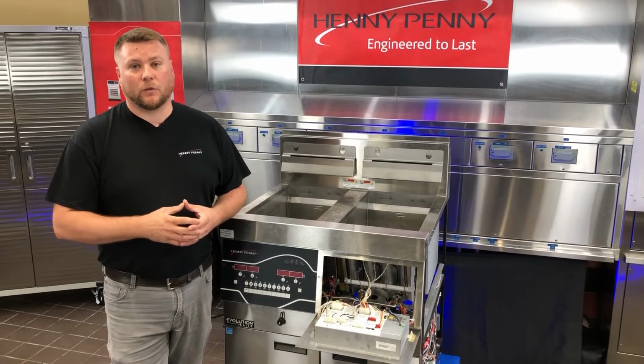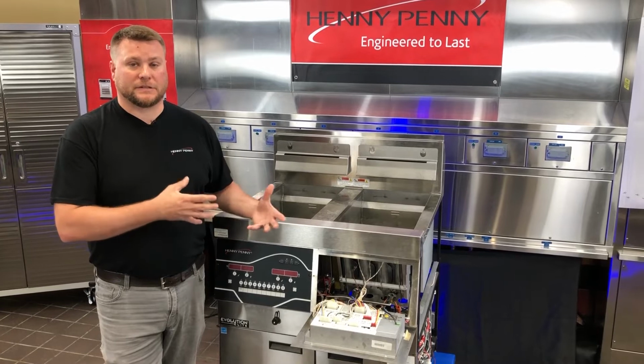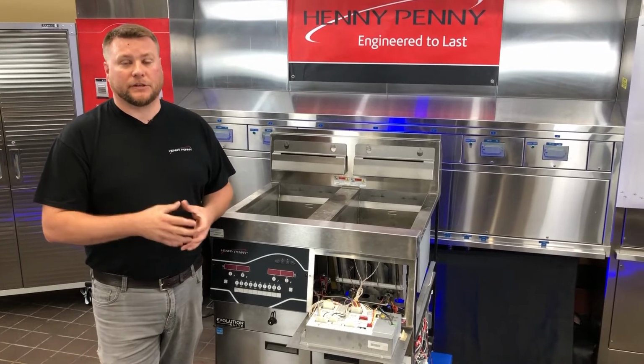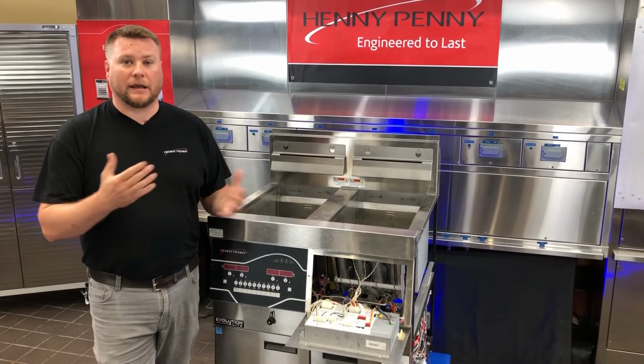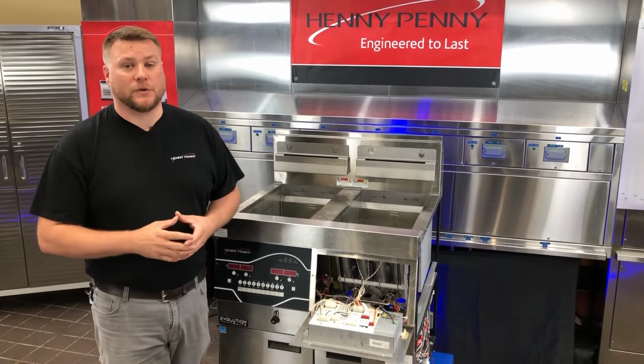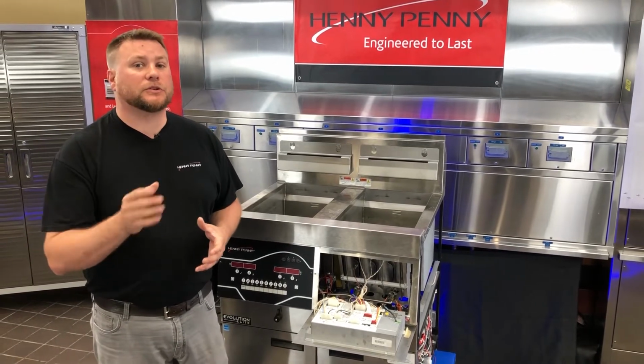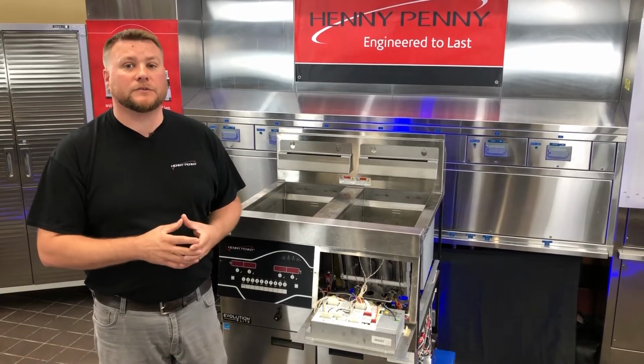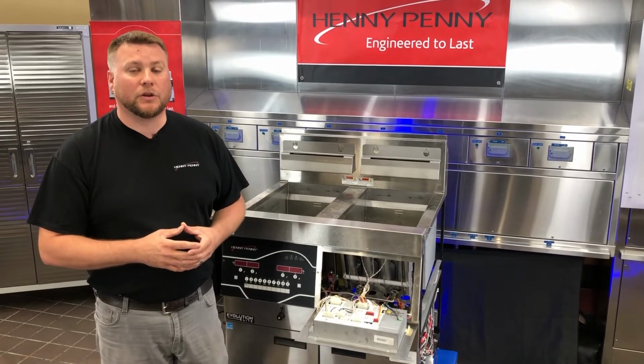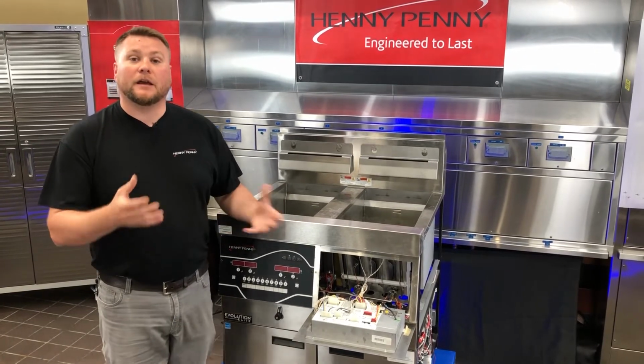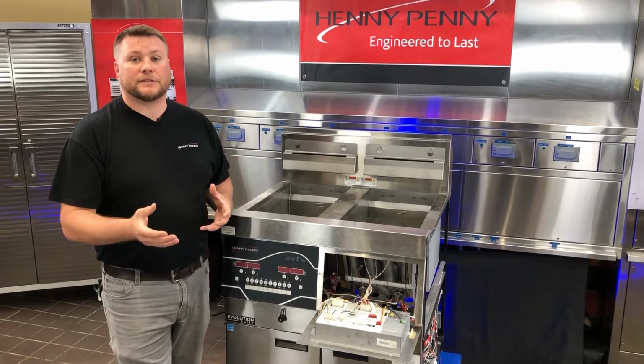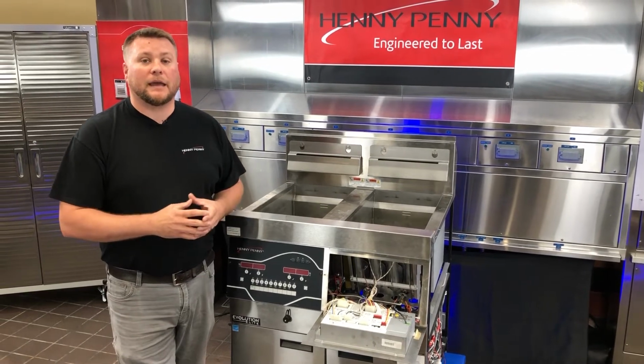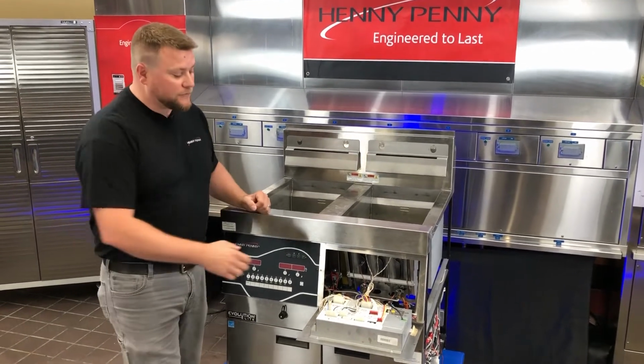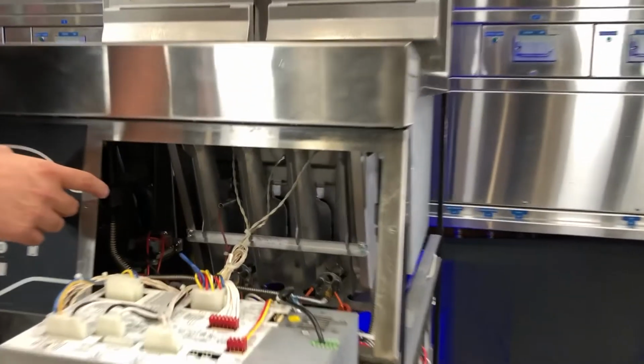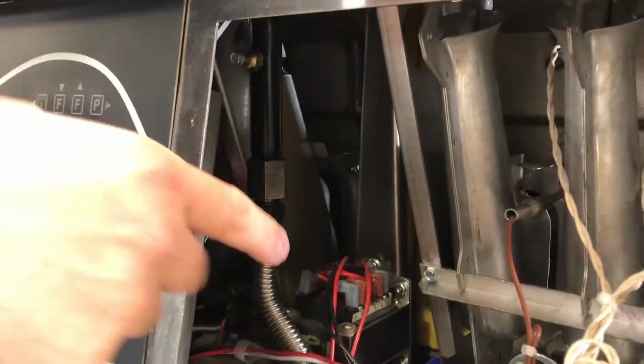One is a 1-amp fuse for domestic gas units, and for electric units with 208 volt and high voltage, you could run into a 1.5-amp fuse. Be sure to check the fuse stamping on the fuse itself if you find one blown and have to replace it. The other component is our transformer that powers up the AIF board for the supply voltage. For gas units, that's located right here behind control panel number 1 and 2, right there.